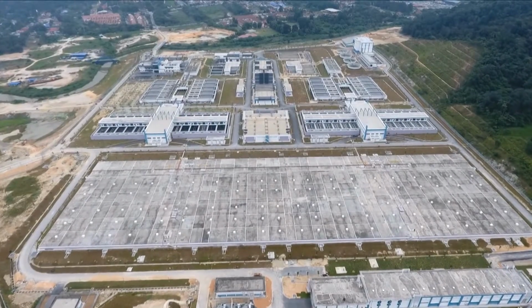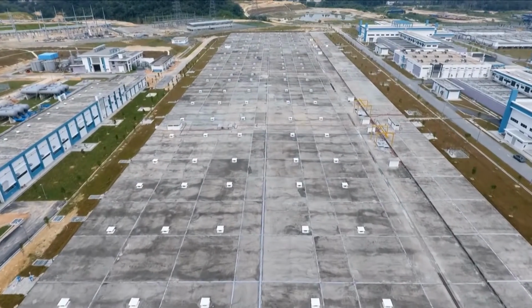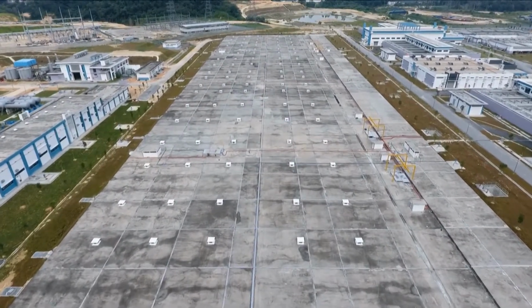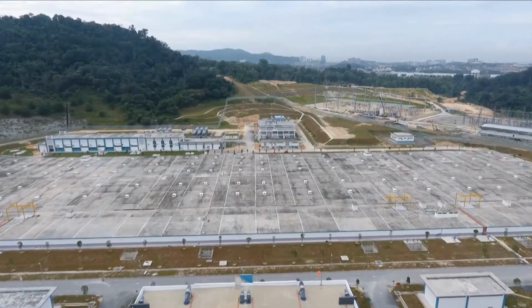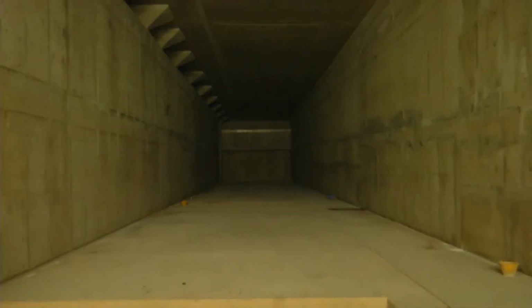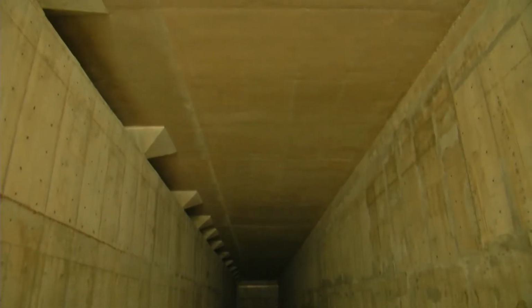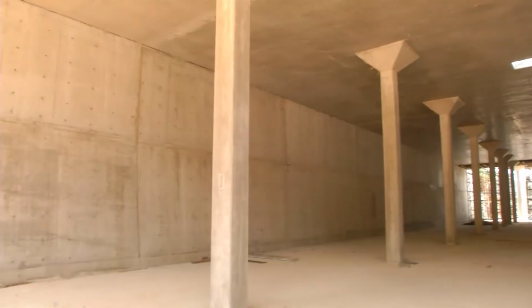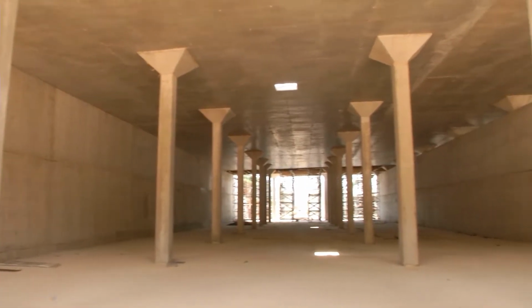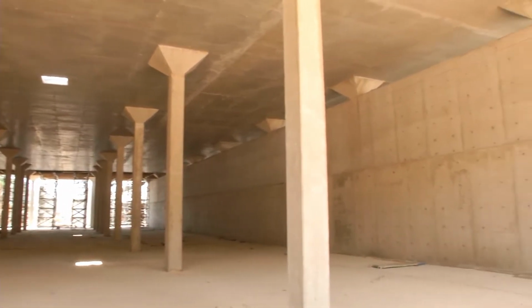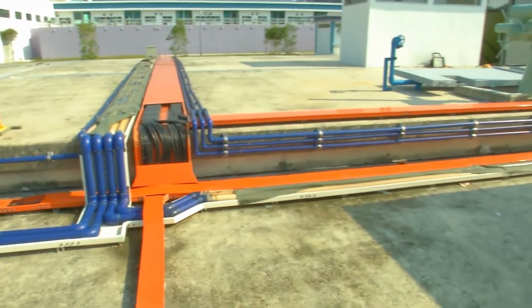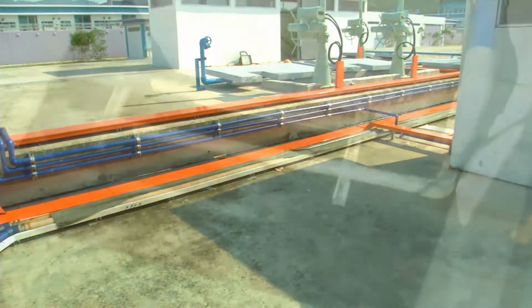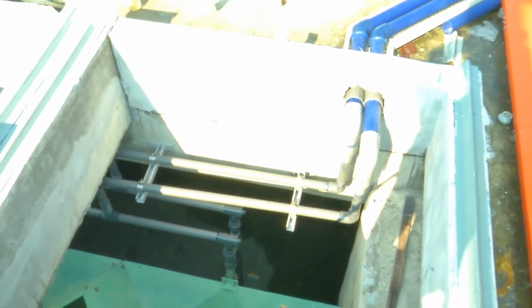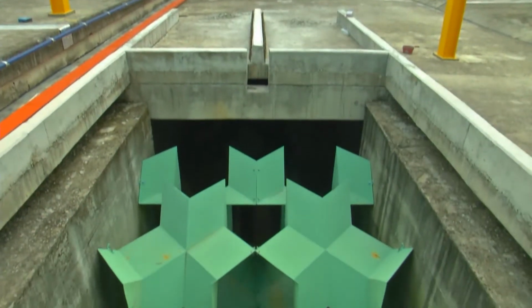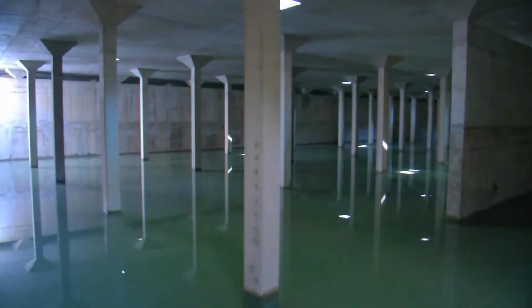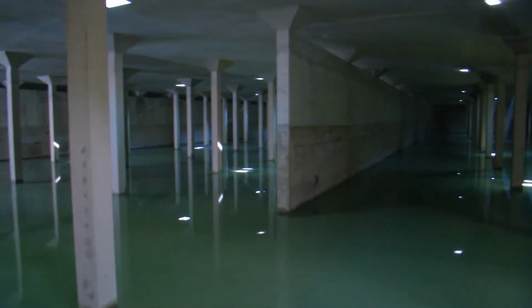Contact tank and clear water tank. Four adjoined reinforced concrete baffled contact tanks and clear water tanks are constructed. The volume of each contact tank is approximately 8,400 cubic meters, and the volume of each clear water tank is approximately 45,000 cubic meters. Fluoride and chlorine shall be dosed before the contact tank, while post-lime is dosed prior to the static channel mixer for pH adjustment. The outlet of the contact tank connects to the clear water tank for storage.